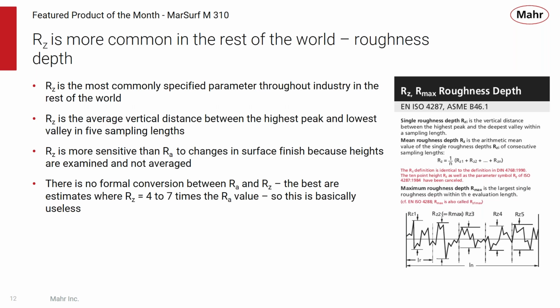Now, RZ is a more common way of analyzing a surface in the rest of the world. It's really roughness depth. So RZ is the most commonly specified parameter throughout the industry for the rest of the world. And RZ is the average vertical distance between the highest peak and the lowest valley within 5 sampling lengths. RZ is a lot more sensitive than RA to changes in surface finish because the heights are examined individually and not averaged out. There is no formal conversion between RA and RZ. You can get estimates of 4 to 7 times the RA value for RZ, but that's a pretty wide discrepancy. So you can have a guesstimate, but if you want to get the right answer, you have to measure and analyze the data with the parameter that's needed.